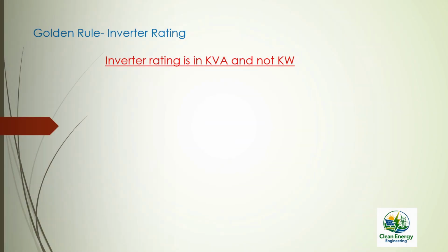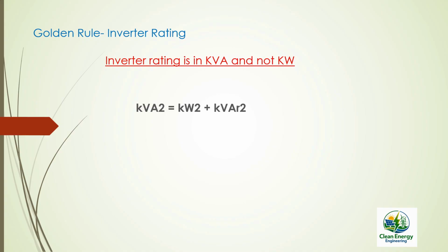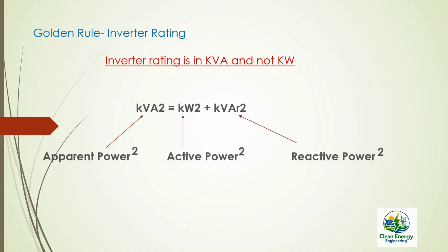Let's start with the golden rule, and honestly it will solve half of the confusion. The inverter is rated in kVA, not kilowatt. So active and reactive power both consume the same inverter capacity rated in kVA. Look at the power triangle where S is kVA, P is kilowatt and Q is kVAr. So whenever reactive power increases, active power must reduce and vice versa. Think of inverter capacity like a fixed size bag. It can be filled with either active power or reactive power or a mix of both.